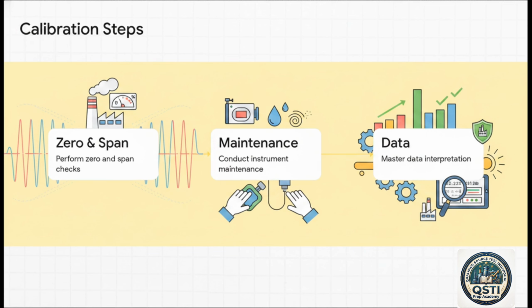Step 2 is conducting regular instrument maintenance. Field conditions are incredibly harsh out there. You're dealing with extreme dust, corrosive gases, heat, moisture. All of that degrades sensitive equipment, and you have to know how to maintain, clean, and recalibrate it right there on site. And step 3, master data interpretation. Once the machine is calibrated and gives you a parts per million reading, what does that actually mean for the facility's compliance limits? Understanding this whole logical flow is how a gas analyzer is rigorously calibrated to yield legally defensible results that will actually hold up to regulatory scrutiny.